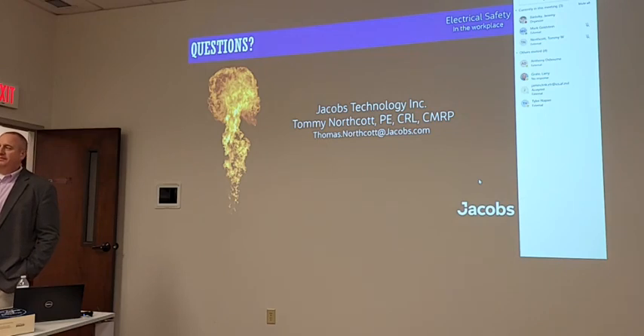Because it was never an issue. I guess you usually think about it in terms of, with the doors closed, I'm not going to cause a fault. I'd have to do something to cause it, and even if I cause it, the enclosure's going to contain it. Generally speaking, that's true, right? What it doesn't do is contain it when the available fault current is above the bracing in the motor control center, and that's where you can get yourself in trouble. But it doesn't mean the standard says that's okay.